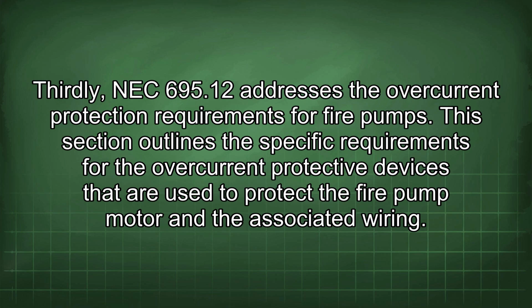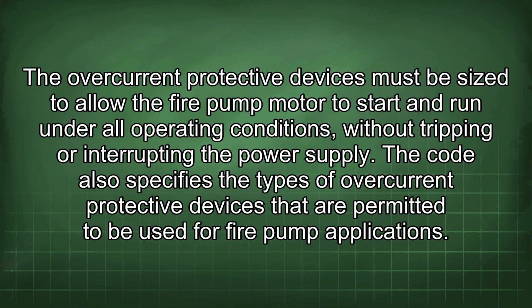695.12 addresses the overcurrent protection requirements for fire pumps. This section outlines the specific requirements for the overcurrent protective devices that are used to protect the fire pump motor and the associated wiring. The overcurrent protective devices must be sized to allow the fire pump motor to start and run under all operating conditions without tripping or interrupting the power supply. The code also specifies the types of overcurrent protective devices that are permitted to be used for fire pump applications.